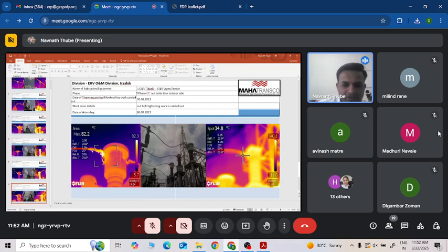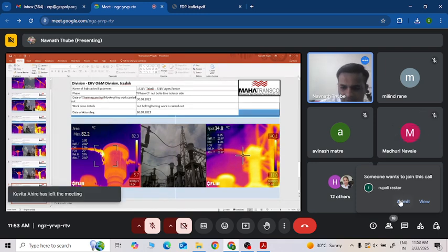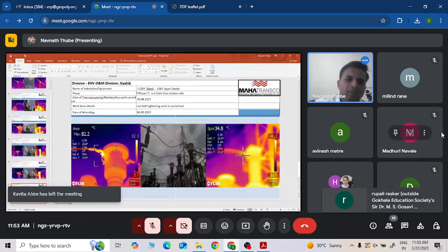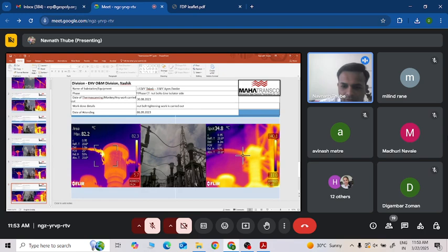Another hotspot was generated at 82.2 degrees. Actually, we consider temperatures above 60 degrees as hotspots and below 60 degrees as normal. Only those attaining 60 degrees and above are hotspots. The actual time of taking these images is the peak load period. As you all know, in the peak load period the load increases and the chances of hotspot generation are greater.